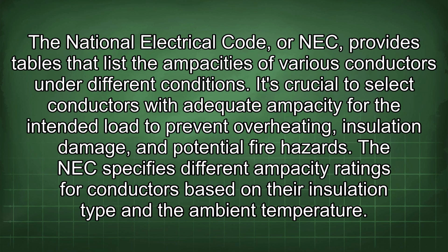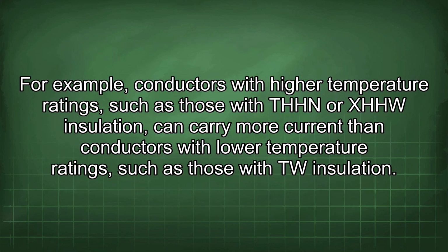It's crucial to select conductors with adequate ampacity for the intended load to prevent overheating, insulation damage, and potential fire hazards. The NEC specifies different ampacity ratings for conductors based on their insulation type and the ambient temperature. For example, conductors with higher temperature ratings, such as those with THHN or XHHW insulation, can carry more current than conductors with lower temperature ratings, such as those with TW insulation.